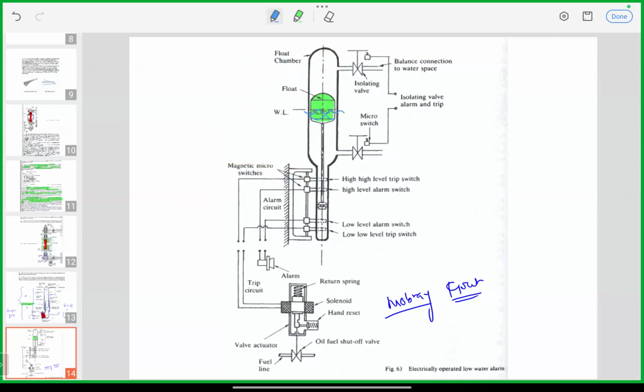This is your water level. There will be an extended arm to this main float, and on the bottom there will again be a small float, which is magnetic in nature. Outside of this float chamber, there will be 4 magnetic micro switches provided. Whenever the level in the boiler reduces, the level will also drop in this float chamber, which allows this magnetic float to move down.